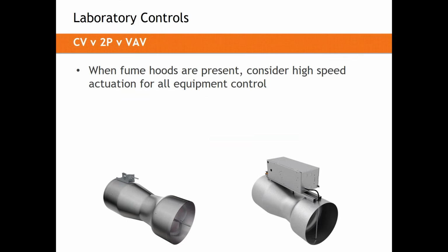Now, when fume hoods are present, essentially all devices in the space should be high speed. So the fume hood itself, number one, whether it's a VAV box, high accuracy terminal, or venturi valve, it should be high speed. The supply and general exhaust should also be high speed. And even the equipment, you should probably consider using high speed actuation. So if you have supply, exhaust, and a fume hood, and you add in a snorkel that's 2-position, for example, that should likely be a high-speed device as well, just so that everything tracks at the same speed.